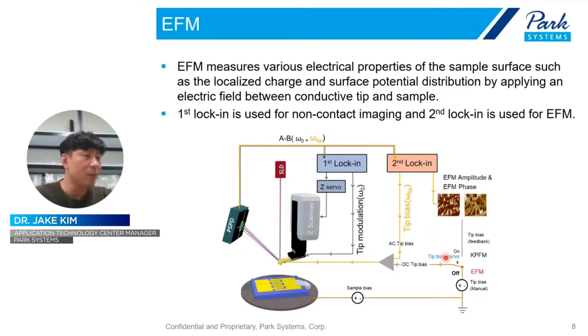And here comes the simple diagram of EFM. Once again, EFM measures the various electrical properties of sample surface, such as localized charge and surface potential distribution by applying an electric field between the conductive AFM tip and sample. And to detect the electrical signal, two lock-in amplifiers are adopted. The first one is for non-contact imaging, and the second one is for the EFM signal. So we can obtain both height, like topography, and the EFM signal simultaneously.